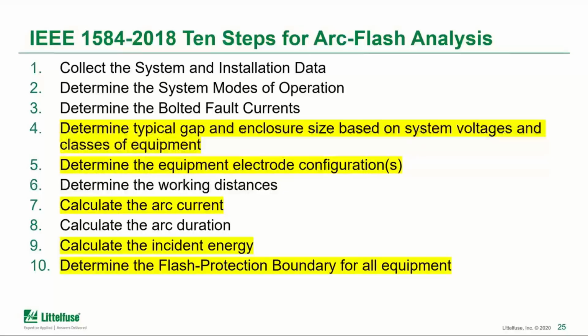And number 10, the flash protection boundary. So the flash protection boundary is still defined as that distance where the incident energy is 1.2 calories per centimeter squared. And overall, I guess as a note, this model is intended to be used by a qualified person who understands and can do the analysis. So it's just a point I want to add in there.